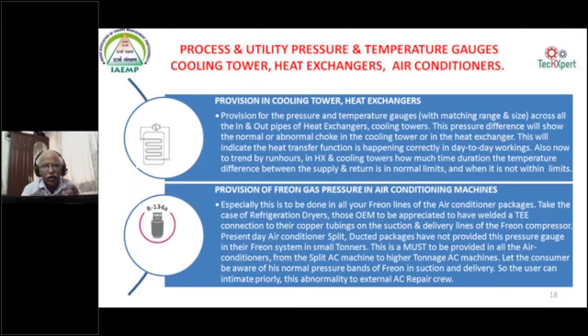Similarly, for an air conditioner, whether split or package, what is the kilowatt input given to the air conditioning machine, and what is the freon output, either the suction pressure or the discharge pressure for the given compressor? The refrigerated dryer manufacturers have given suction pressure and delivery pressure to be monitored. Similarly, we can have this on all our air conditioning systems, right from a 3-tonner or a 5-tonner or any of the sizes, including the split, depending on the condition where it is critically used, for example on an open terrace in an unmanned area. At least if the freon gas is leaking out, everything you can come to know by having these gauges within the compressor hood as such.